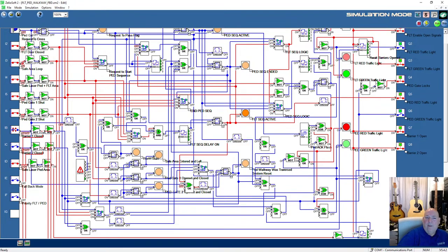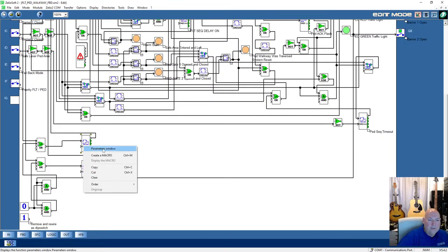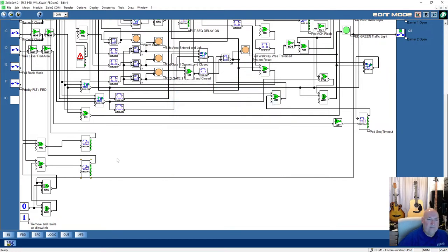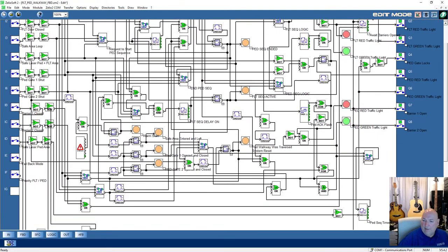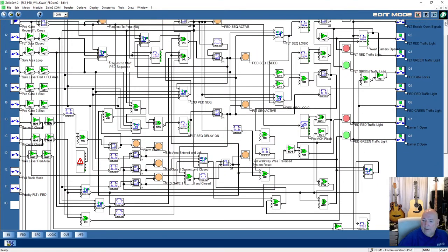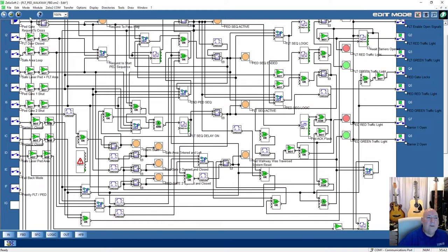So I think what happened, I got the wrong times around the wrong way. Let's just try something. Go down here and swap these delay times round. So we want 5 up here and 30 down here. And 5 up here and 30 down here. Alright, so that's 5 is 500 milliseconds, 30 is 3 seconds. Right, let's make sure we can see the numbers. Oh, we can see it. Make sure we can still see the numbers. I think it's there, isn't it? Or is it that one? Can't remember. Right, save it.